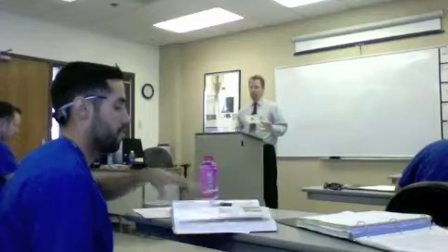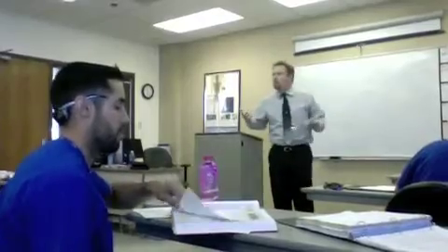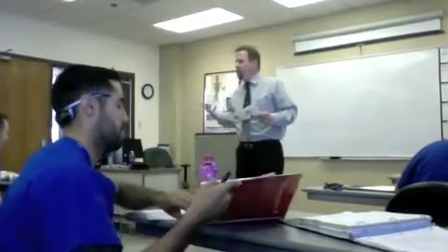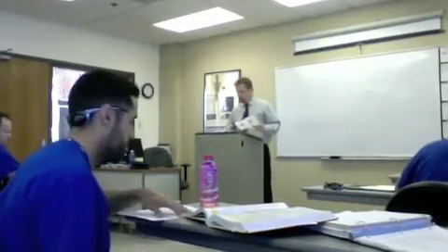Anytime you use a grid, you have an increase in contrast. Does that make sense? It cleans up scatter, therefore you have more of a black and white image. Gustav Bucky came up with that when? 1913? When was it? 1913, okay? That was a few years after. But the images were so grayed out, they had to do something. We need to clean up the images. What can we do?